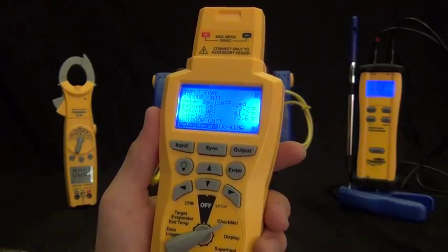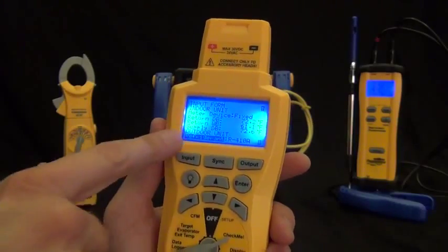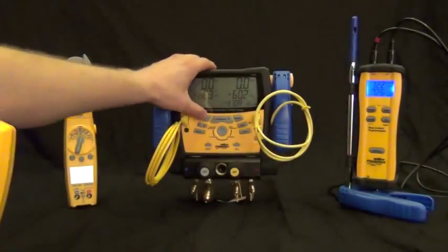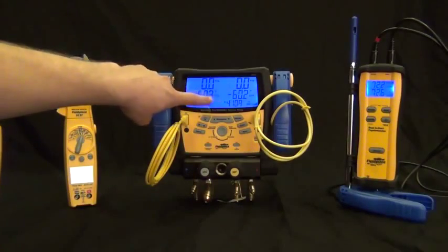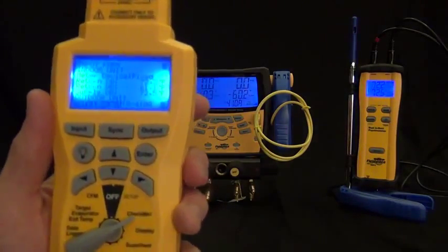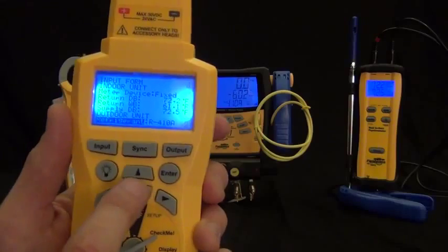Then I have my refrigerant. My refrigerant is actually being sent wirelessly from the SMAN4. So I plug in what the refrigerant is on my system to the SMAN4, and the SMAN4 tells the HG3 what to display and what to use for the PT charts.